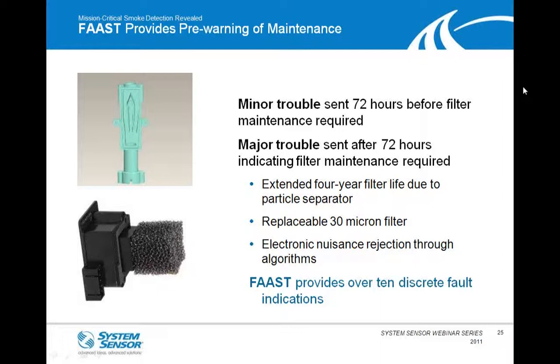In addition to this is just one example of one of the trouble conditions that you could get from a FAAST device. FAAST actually provides over 10 discrete fault indications. The nice thing about it, again, some of those are major in nature that need to be addressed immediately and could compromise the device. The majority of those are more of the minor area that, again, based on the standards and the way that standard was written for trouble conditions, could be delayed till that next working day. So, you know, the old adage that you get that notification at 3 a.m. on a Saturday, it allows you to give you at least 24 hours in order to address it.